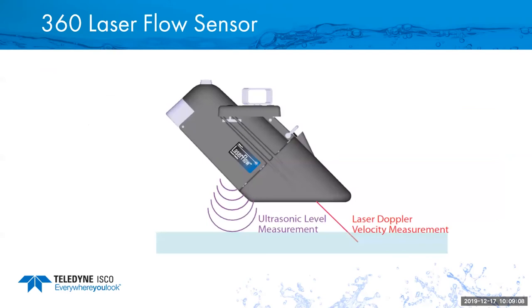Now, the laser flow sensor works on the same kind of principle as the 350, but it's non-contact and also uses a laser instead of a sound wave in the water. What the 360 laser flow does is it uses the ultrasonic sensor mounted on the back of the laser flow to measure the depth of the water and then measures the velocity, I should say, using the laser under the surface of the water. It measures the velocity of the particles in the water and therefore can calculate your flow rate.